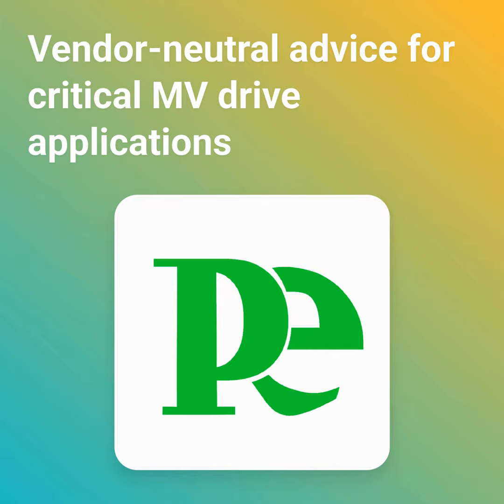Things highlighted in your sources include modularity. How easy is it to swap a failed part, like a power cell? Fault containment within the drive helps too, and vendor support is massive: skilled techs, parts availability, remote diagnostics. Remote support can save a site visit sometimes. Absolutely. It can slash troubleshooting time. Now, for building that high MTBF, high reliability from the start, what's key there?